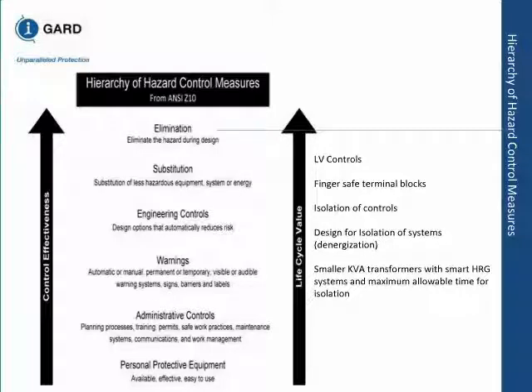One thing you can also do is use smaller kVA transformers. Larger transformers contribute a lot of fault current, and that creates an arc flash hazard. Of course, to do that, you have to design the system. Transformer size is basically controlled by the largest motor. Instead of using a 3000 kVA transformer, you can use two 1500. Initial cost will be higher, no doubt about it. But in life cycle cost, industry experience is that one arc flash fatality is close to $1.5 million. An arc flash third-degree burn injury is close to $6 million. So you can see how much money you can save.